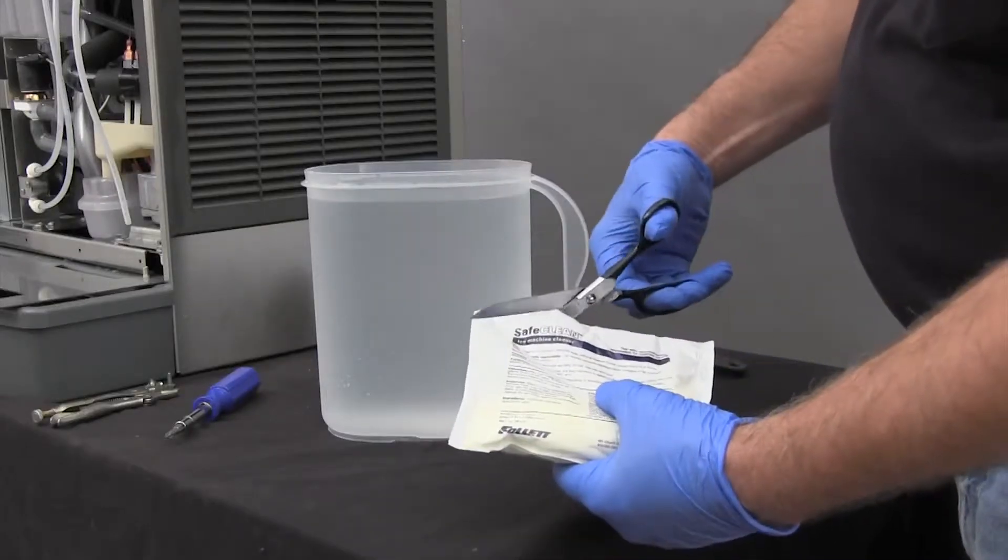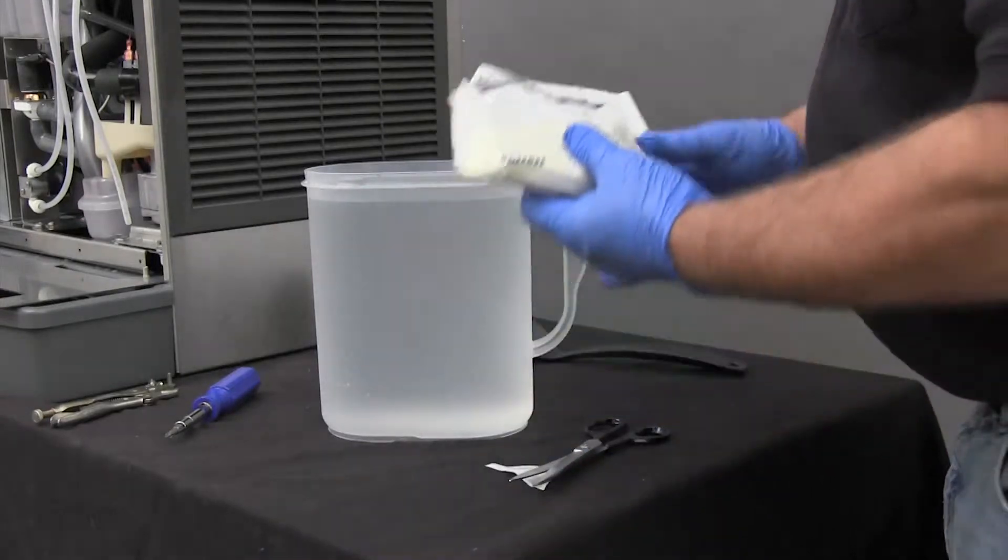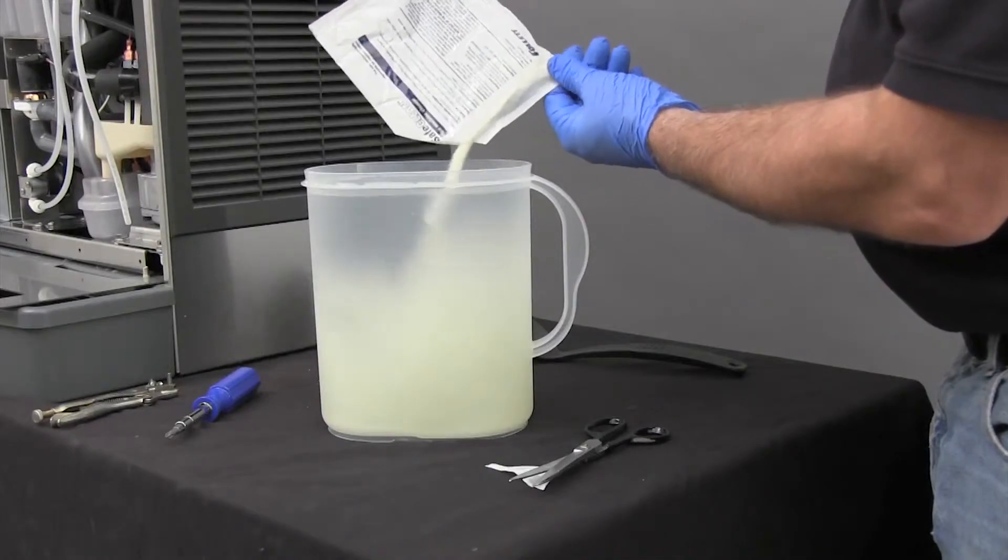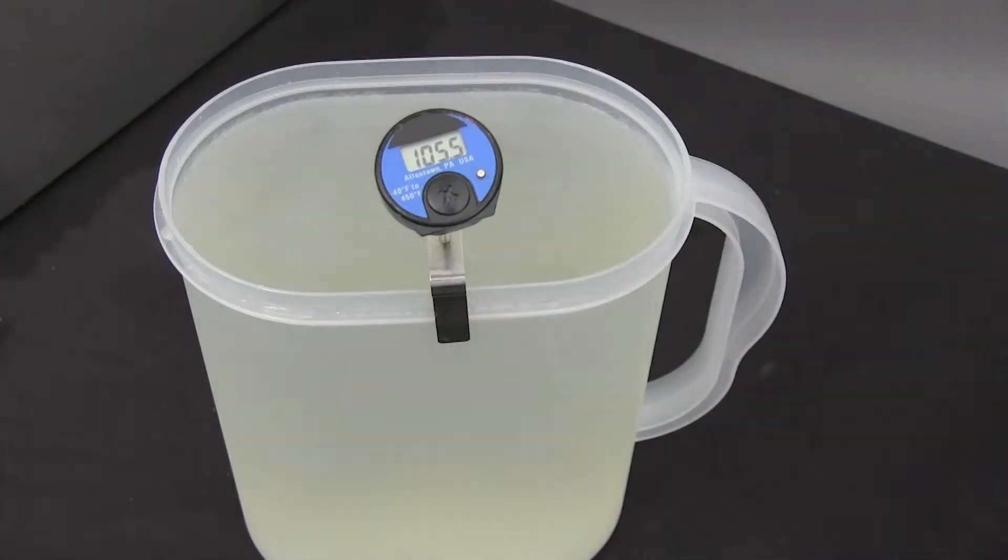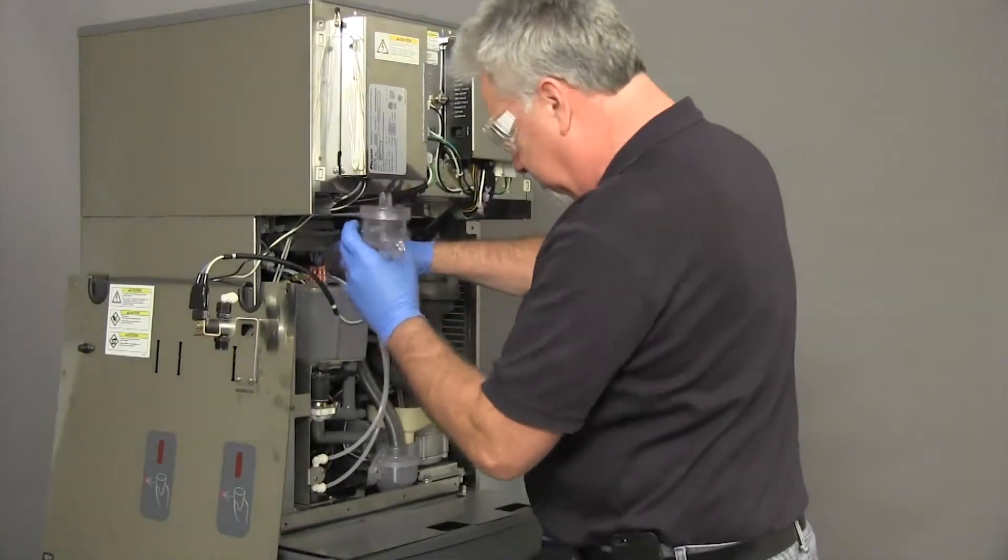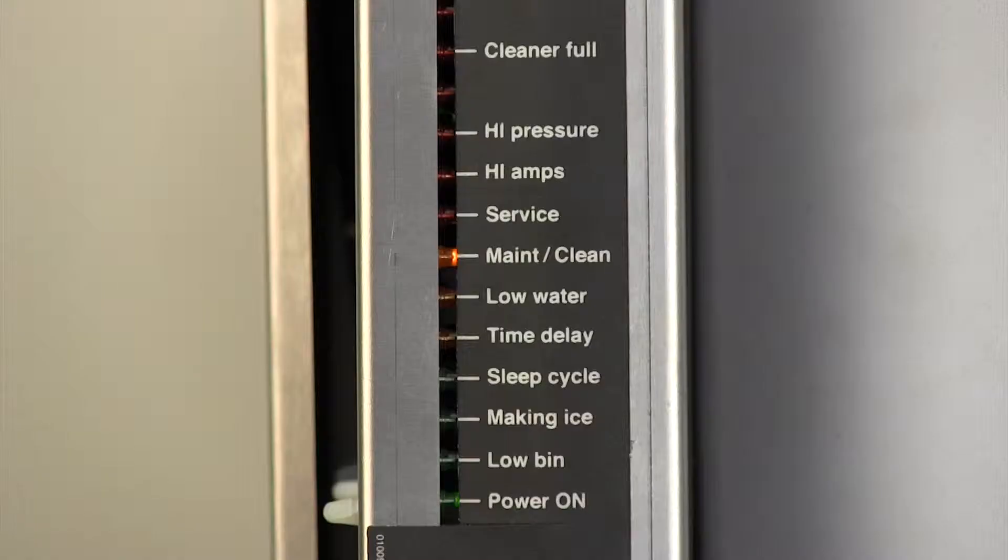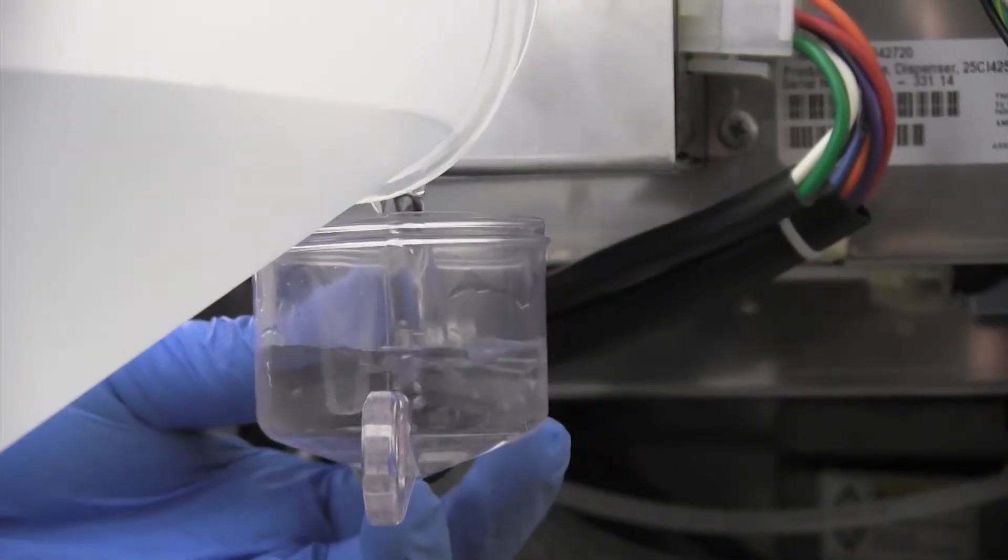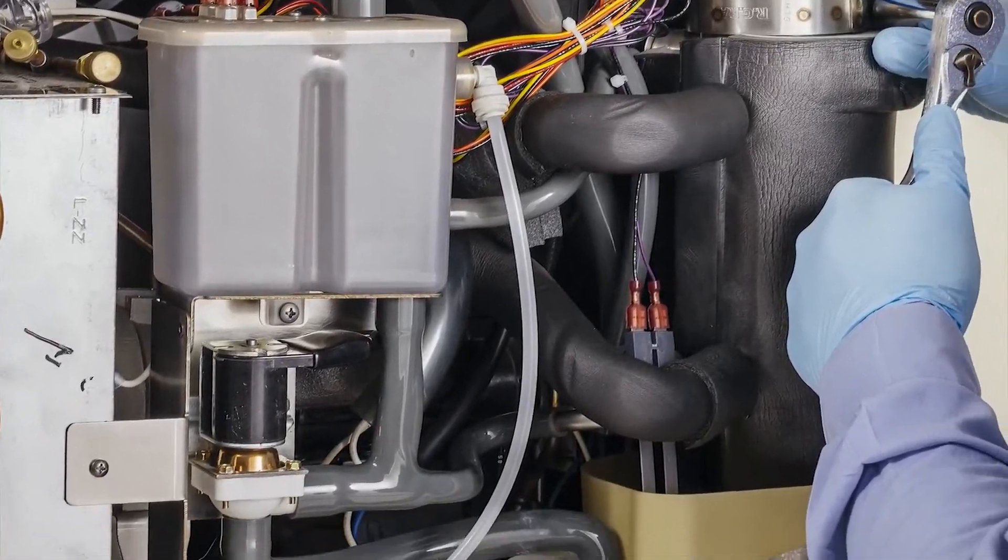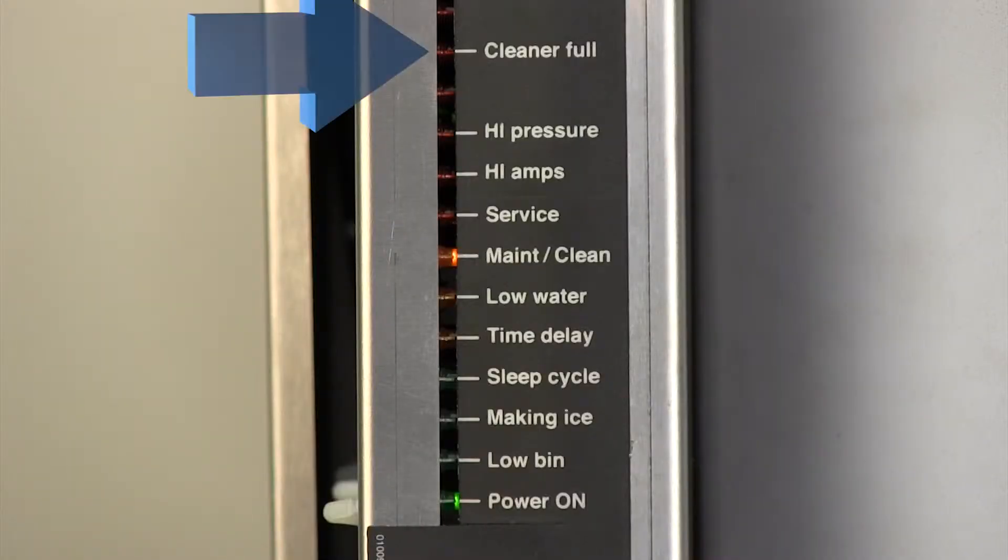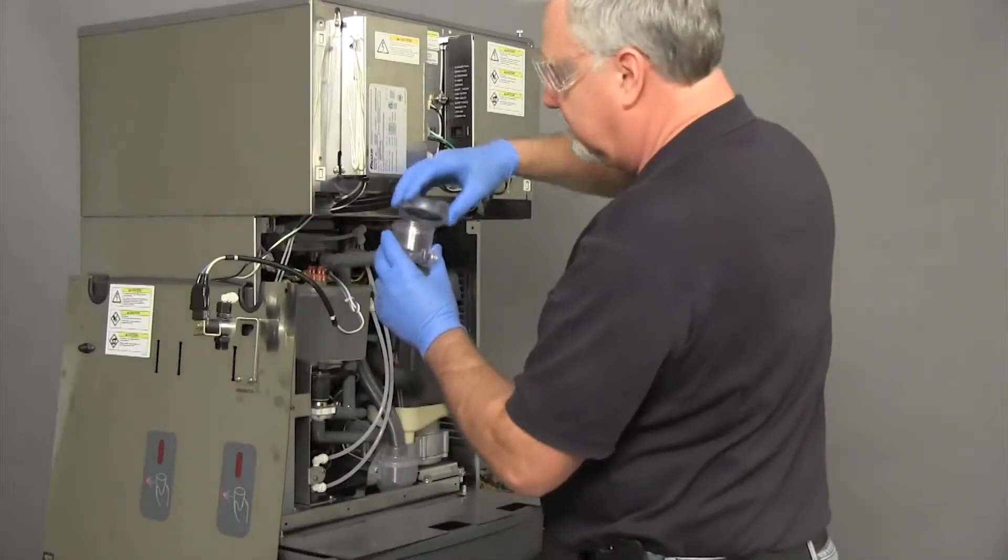Following the manufacturer's instructions, mix one 7-ounce packet of Follett SafeClean Ice Machine Cleaner and Descaler with one gallon of water that is at least 100 degrees Fahrenheit. Locate the cleaning cup and remove the lid. When the low-water light comes on, elevate the cleaning cup above the water reservoir. Slowly add solution to the cup until the solution is going through the overflow tube to the evaporator drain pan. Verify that the cleaner full light turns on. Replace the cup lid.